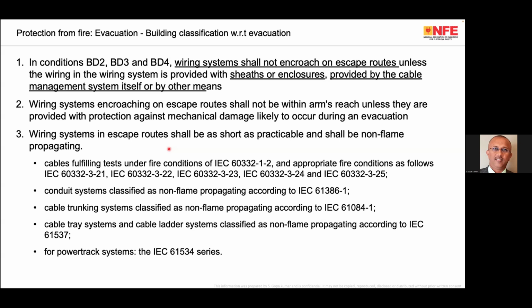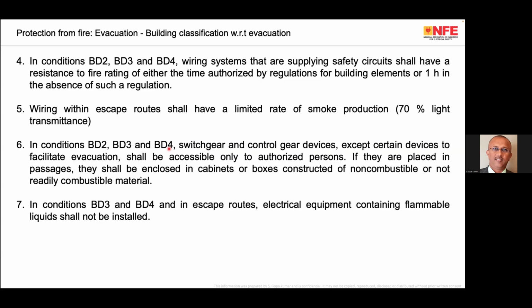That means the wires used in this area, especially escape routes in BD2, BD3, BD4, should be halogen-free wire, not the normal wires, halogen-free, which is a special wire. Similarly, in locations BD3, BD4, wiring system supplying safety circuits shall have a fire resistance of minimum 1 hour or 2 hours. Wiring system within the escape route shall have a minimum rate of smoke production of 70% light transmittance. Sorry, not 60%, but 70% light transmittance, which means the smoke concentration must be very low. It should be a halogen-free wire.